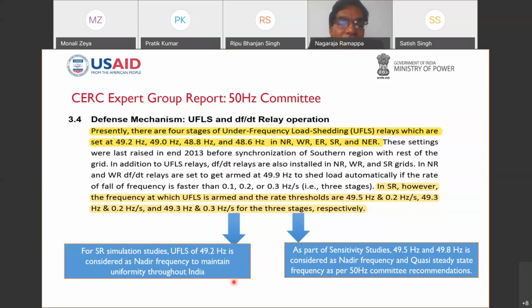Therefore, in the southern region simulation studies, 49.2 Hertz has been considered because in the southern region, the under frequency load shedding alarm is at 49.5 Hertz, and then at 49.3 Hertz, and at 0.2 Hertz per second rate of change of frequency, the load shedding is happening. And as part of the sensitivity studies, we have also done the studies for 49.5 Hertz and also 49.8 Hertz, for the quasi-steady state frequency and also the nadir frequency of 49.5, but the 49.8 is considered for the quasi-steady state frequencies. Next, please.